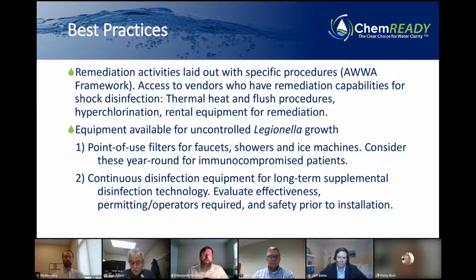In addition, if you have long-term or recurring positive Legionella results, consider having continuous disinfection equipment installed in your facility. This isn't a fit for every facility, and it's not a recommendation I make for every customer. But if you have continued positive results and the city doesn't supply enough disinfection for your water, or you have plumbing issues in your buildings, you should evaluate the effectiveness, the permitting and operators required, and the safety before installing one of these supplemental disinfection systems. It can be an effective treatment for limiting bacteria growth.